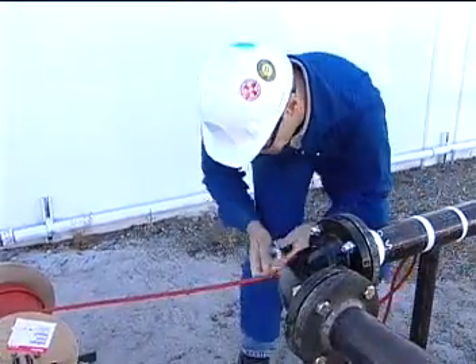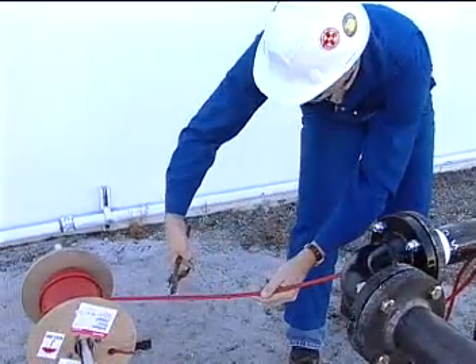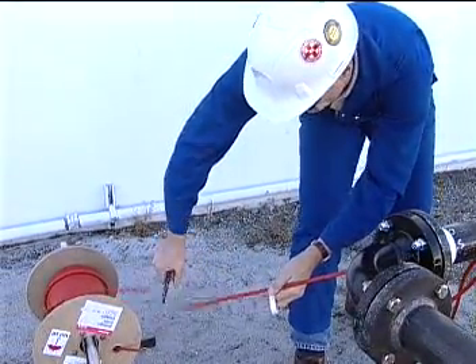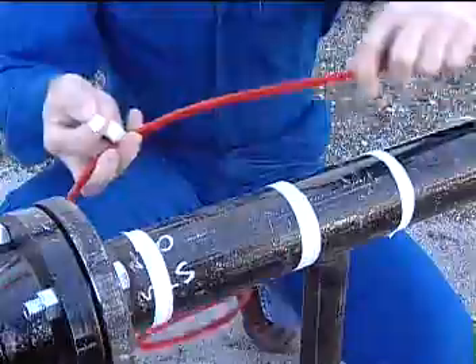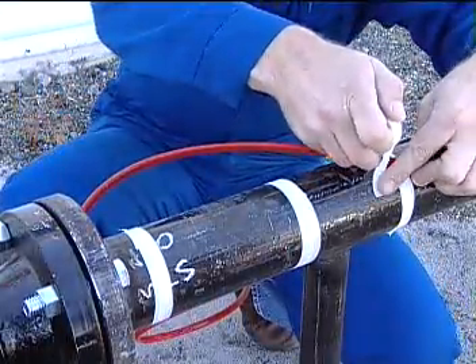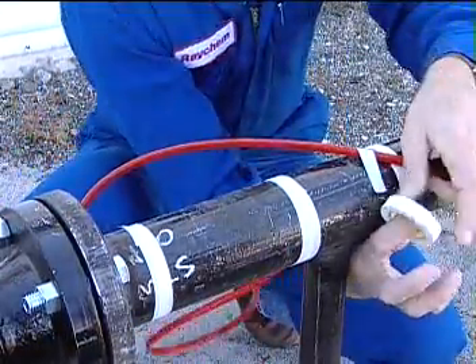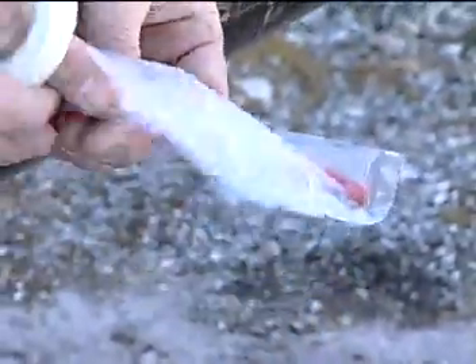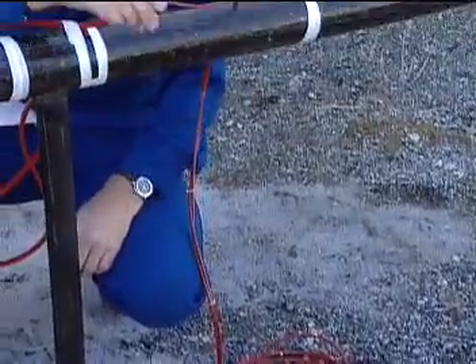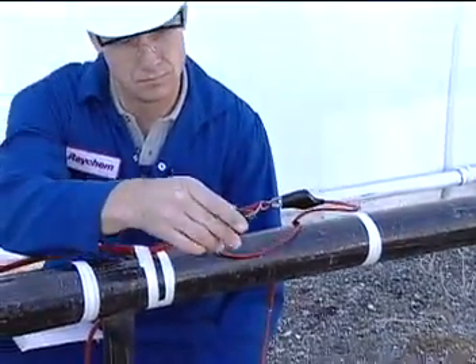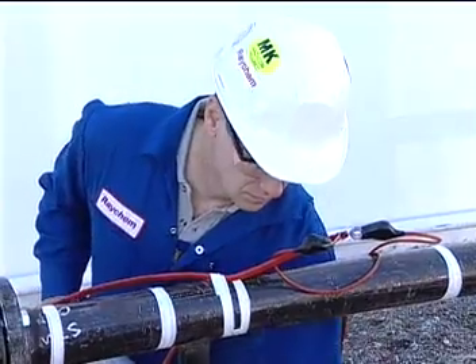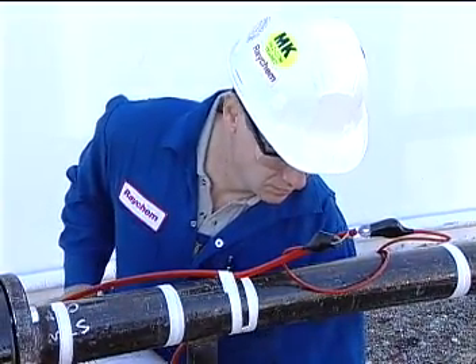Once you've worked your way back to the cable reel, cut the heater cable from the reel and leave a minimum 18-inch service loop for the power connection. Then tape the cable to the pipe. If the cable will not be immediately terminated, tape a plastic bag over the end to protect it from moisture. Now, conduct an insulation resistance test on the cable again to make sure that the cable has not been damaged. Record the reading in the manual.